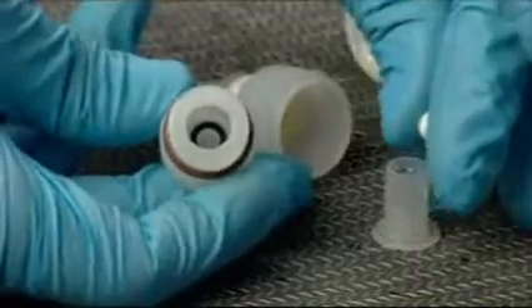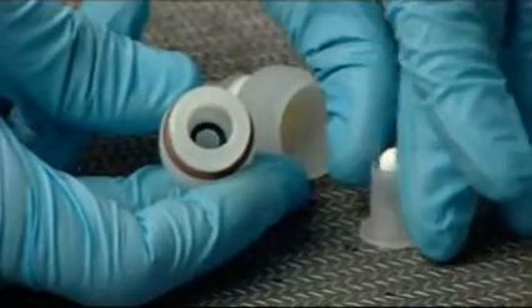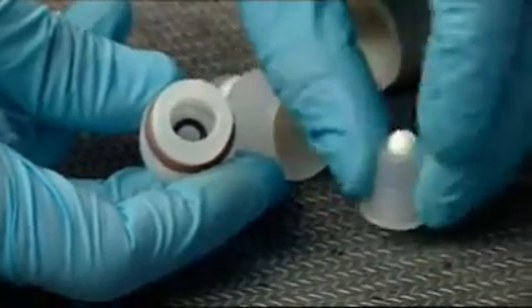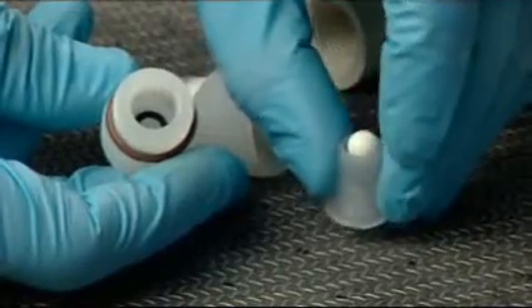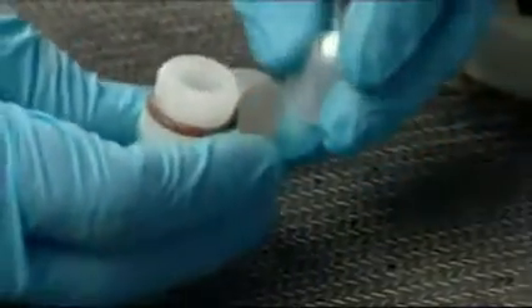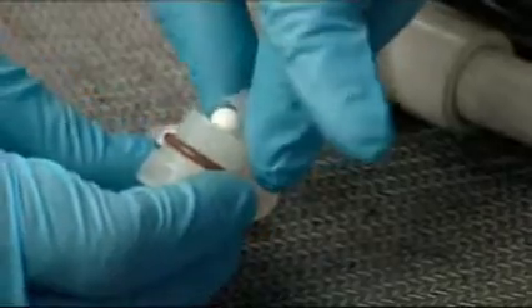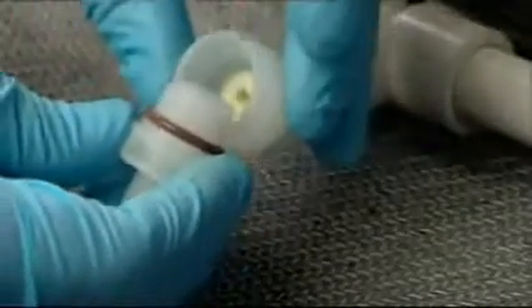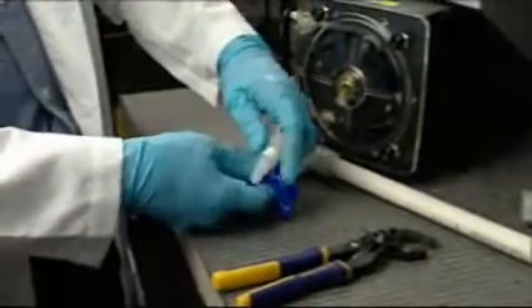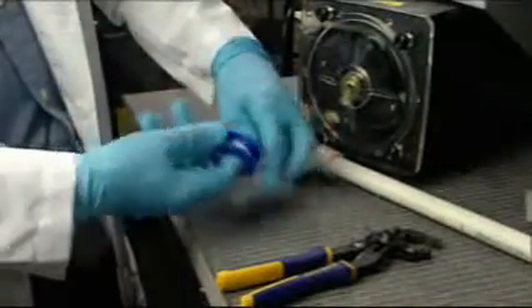Note that it adds additional back pressure, especially when pumping viscous fluids. The ceramic ball valve should be very smooth to ensure a proper seal. Replace if necessary. The ceramic ball valve is required. However, the duckbill valve is not required and may be removed. Wrap the threads with Teflon tape and reinstall the fitting in the piping system.